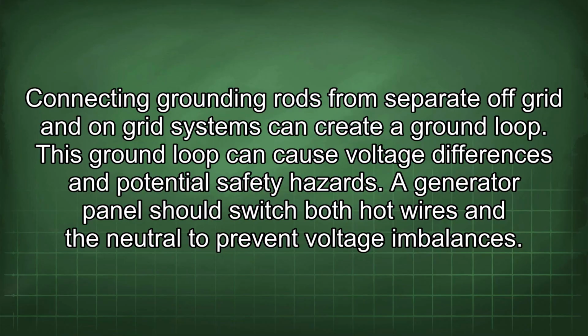Connecting grounding rods from separate off-grid and on-grid systems can create a ground loop. This ground loop can cause voltage differences and potential safety hazards. A generator panel should switch both hot wires and the neutral to prevent voltage imbalances.